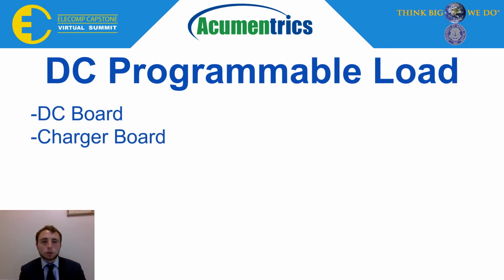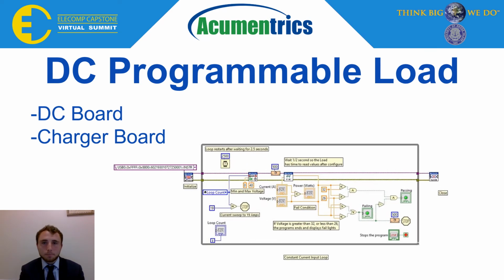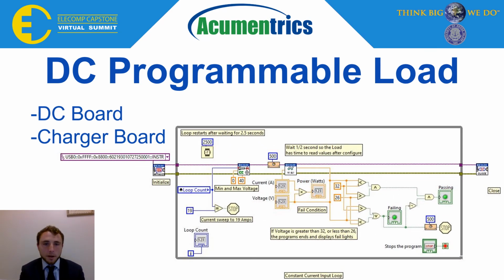This is the DC board and charger board DC programmable load VI. It starts off by initializing the loads into LabVIEW so LabVIEW knows which unit is being tested. The code is designed to ramp up the current from 1 to 19 amps every 2.5 seconds.